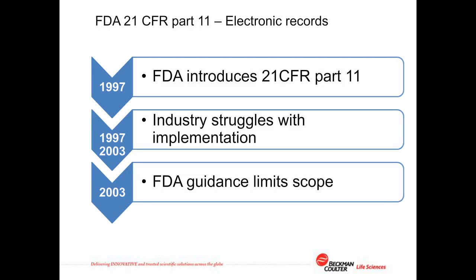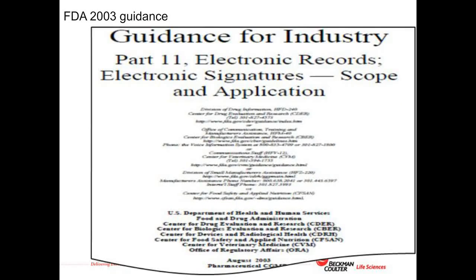The FDA realized that the pharmaceutical industry were taking their guidance as all-encompassing and, recognizing the need for clarity, they issued further guidance back in 2003. This effectively limited the scope of the 21 CFR Part 11 ruling to those records that are either directly covered by the FDA regulations or those that are submitted to the FDA under the Federal Food and Drug Cosmetic Act of 1938 and the Public Health Service Act of 1944. The FDA's 2003 document provided detailed descriptions of those records where 21 CFR Part 11 should be strictly applied, and it dispelled some common misconceptions that may surprise you.